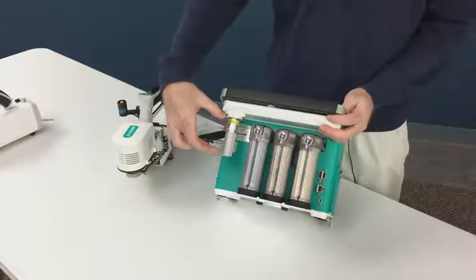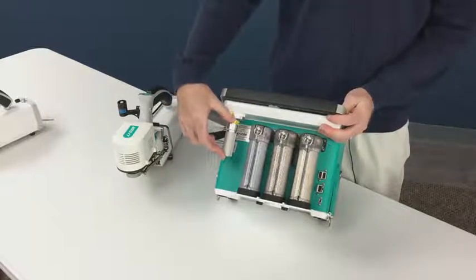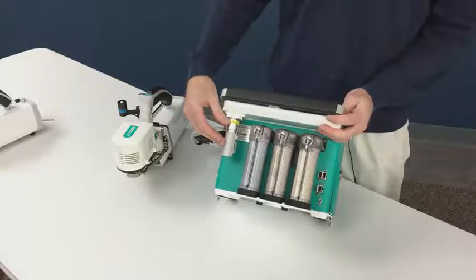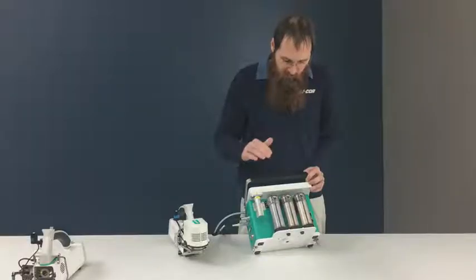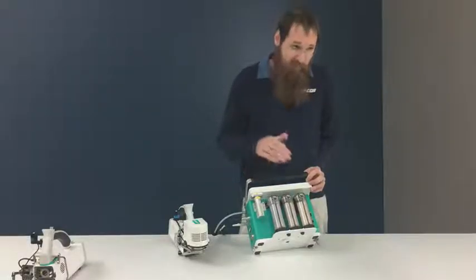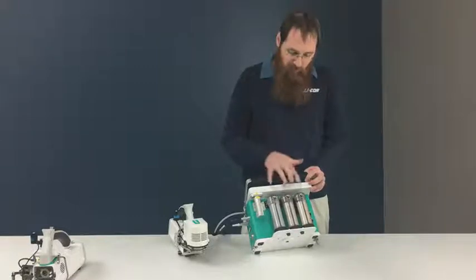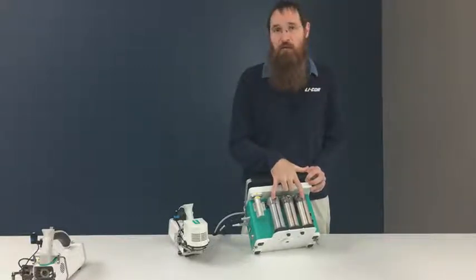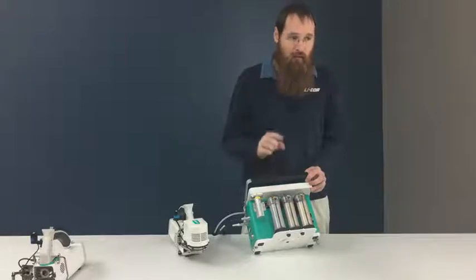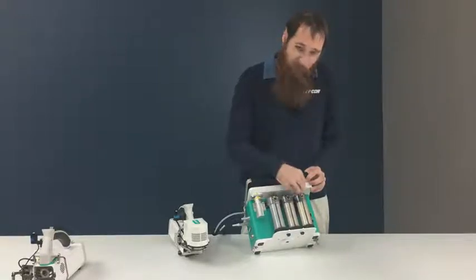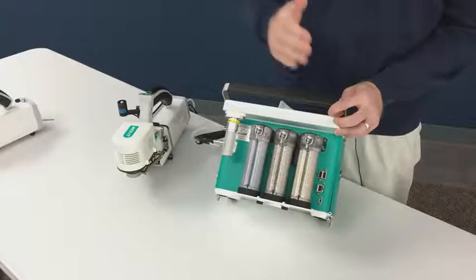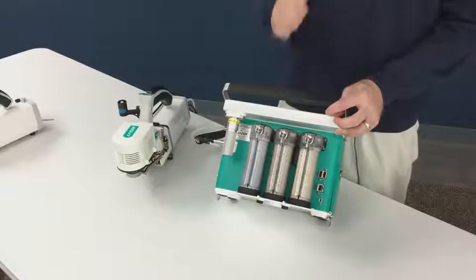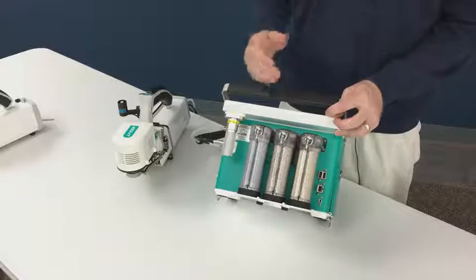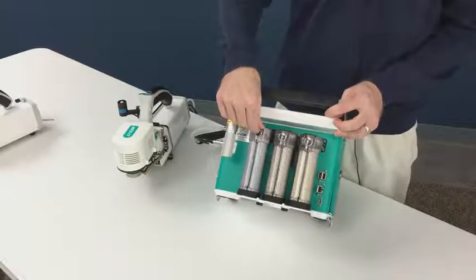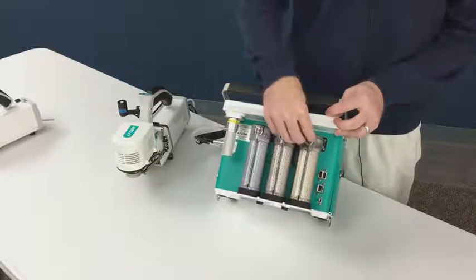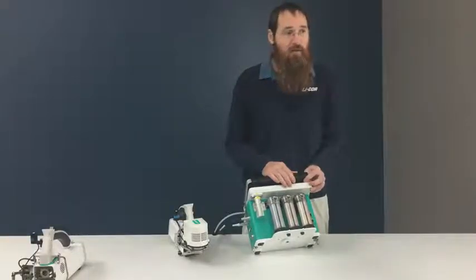And then we have a source assembly for carbon dioxide, and this takes an 8-gram CO2 cartridge. So, some neat things that I want to point out here. If you were a 6400 user, your instrument would have the equivalent of these two chemical columns. And your instrument has a knob at the top of both of them, right? And that knob allows the user of a 6400 to manually set the flow through those chemical columns, right? You can set what proportion of air you want to dry out. You can set whether you want to scrub CO2 or not scrub CO2.